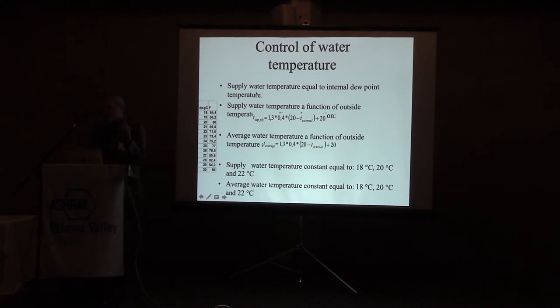So the maximum cooling you can provide is by having the supply water temperature equal to the dew point. That's the maximum you can obtain. But normally, as you will see, this is not a good idea. We need to control the supply water temperature as a function of external temperature, and in some cases it could also be a function of internal temperature. Some manufacturers have algorithms they are using. We could also think about, and I'll show you one building where we tried that, running with the same constant temperature the whole year round.